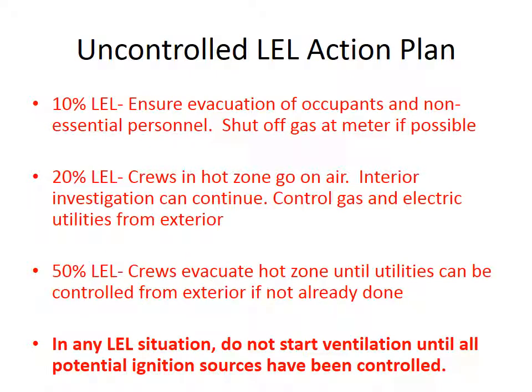Okay, we have an uncontrolled natural gas leak. What that should read is uncontrolled combustible gas leak, and an LEL action plan based on having an uncontrolled leak. We have an uncontrolled source, don't know what it is yet. So here are the different levels. At 10%, like I mentioned before, ensure evacuation of the occupants and non-essential personnel and shut off the gas meter if possible.